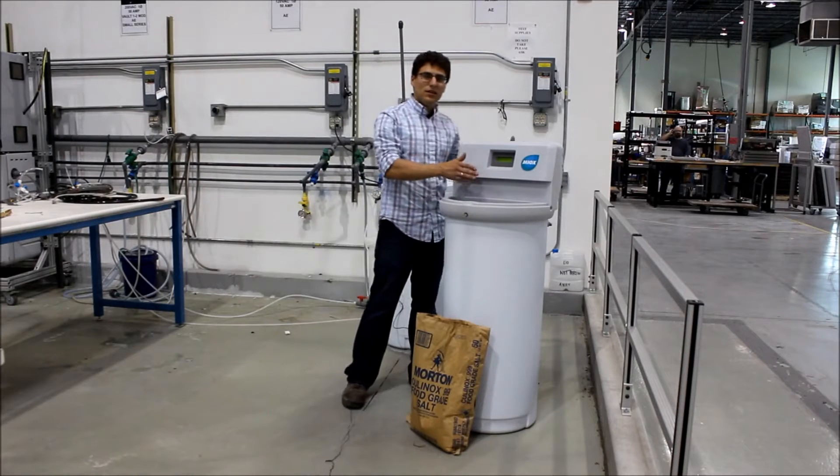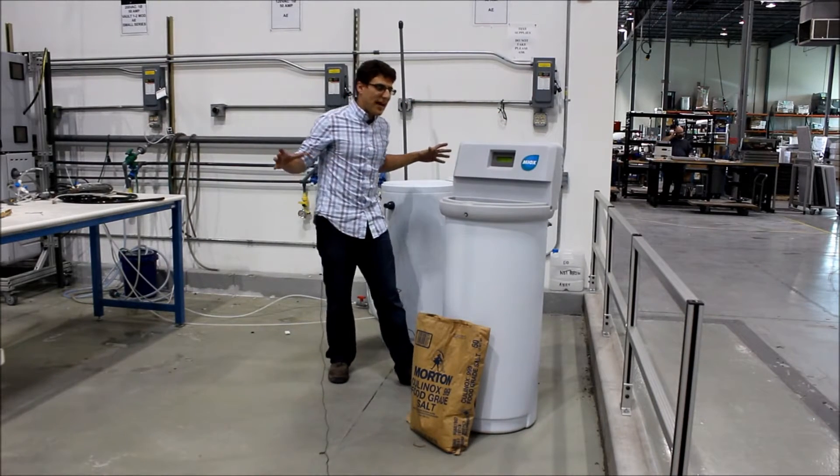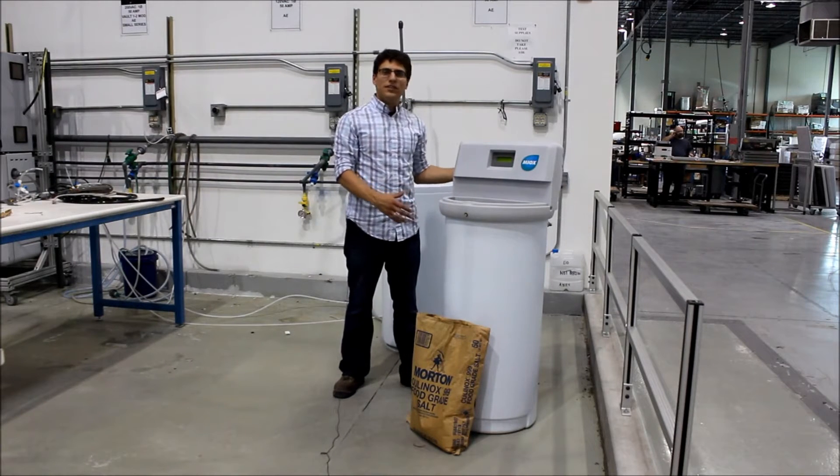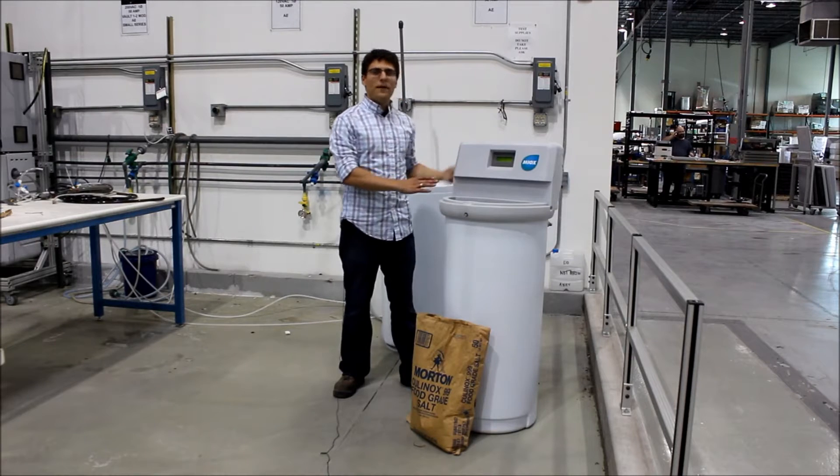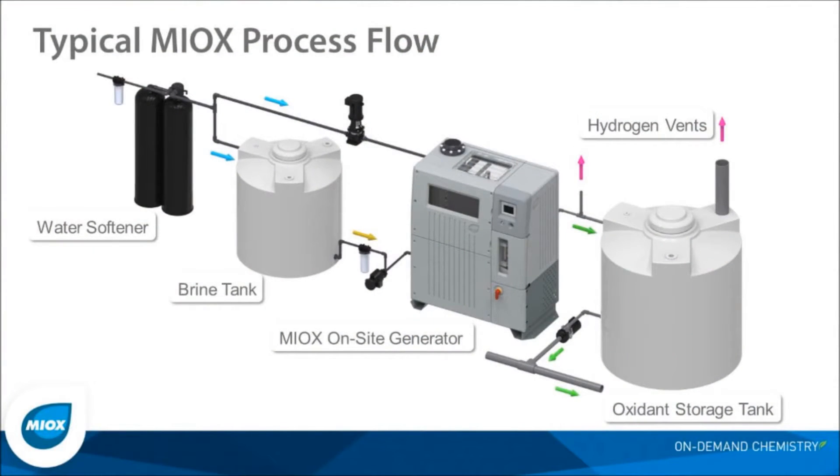So what we're going to do is go through all the parts that we'd like to have leading up to the unit in the process flow, and once we've seen that we'll take a look at the IO of this and go through the flow path and all the components inside. A typical MIOX process flow involves flowing fresh water through a softener and into a brine tank and the OSG. A solution comes out of the brine tank and is merged with fresh water in the on-site generator, passing an electric cell to produce a disinfectant chemistry.